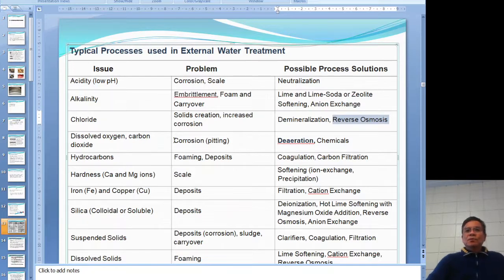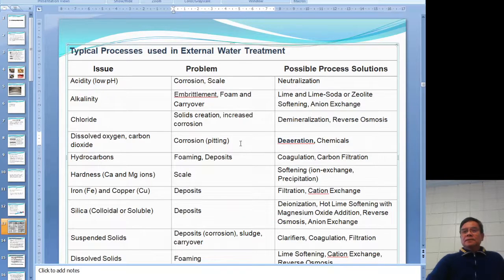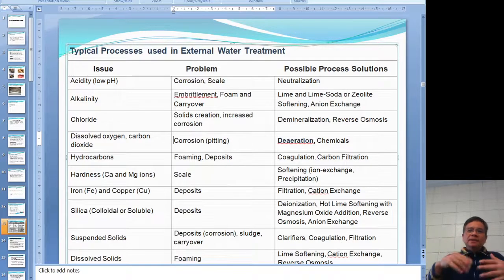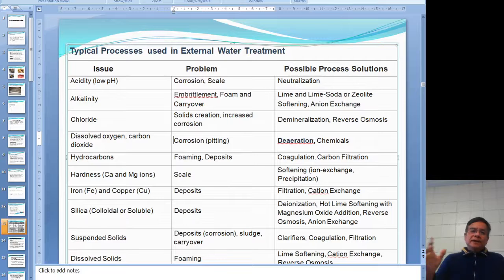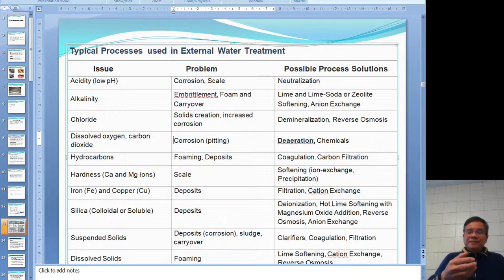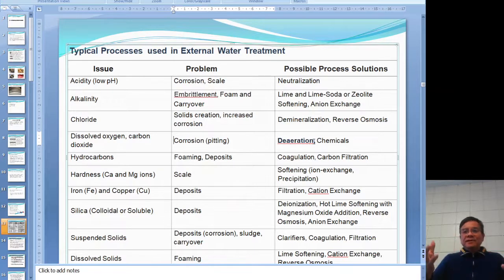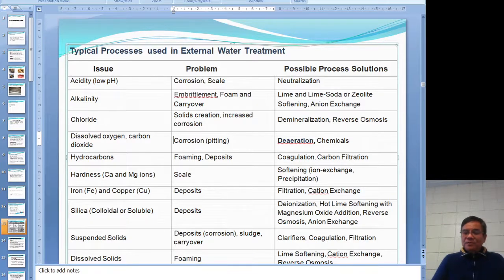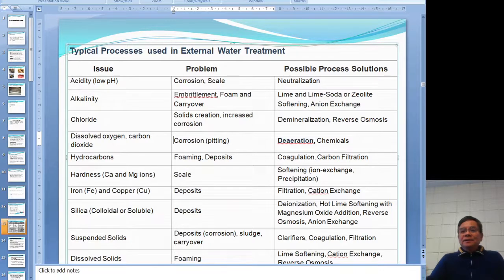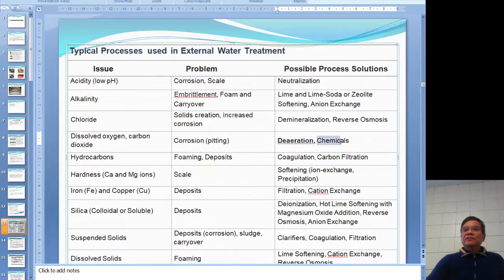For dissolved oxygen, which causes corrosion and pitting, the solution is de-aeration. Every plant has a de-aerator to remove air. However, the de-aerator is not 100% efficient, so after the de-aerator and before the boiler, you still need to add a chemical — sodium sulfite — to treat the remaining oxygen.